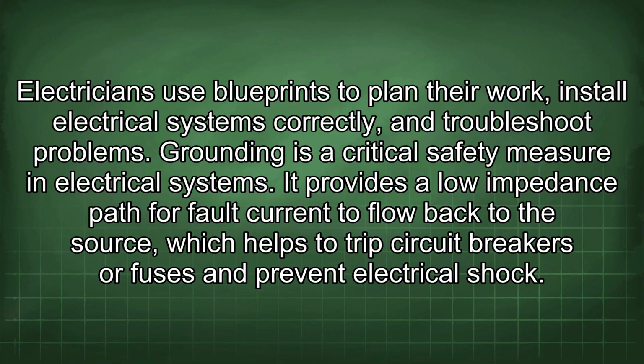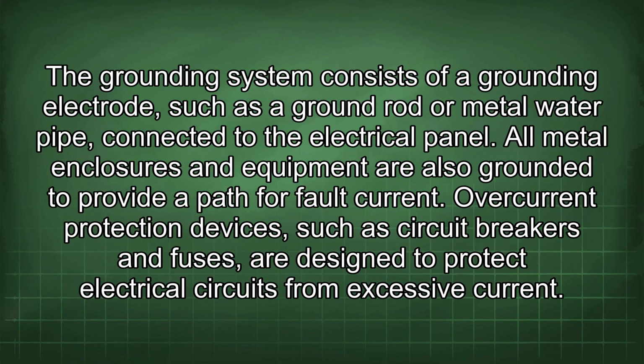Grounding is a critical safety measure in electrical systems. It provides a low impedance path for fault current to flow back to the source, which helps to trip circuit breakers or fuses and prevent electrical shock. The grounding system consists of a grounding electrode, such as a ground rod or metal water pipe, connected to the electrical panel. All metal enclosures and equipment are also grounded to provide a path for fault current.